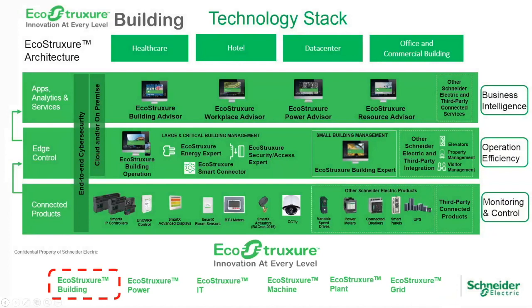If I were here five or ten years ago presenting a BAS system, you might have seen one line at the top representing your IP, internet connectivity, 100 meg. You'd have computers, smartphones, servers at the top, with lines running down to field devices, similar to what we saw in the BAS 101 presentation. Those lines represented BACnet over MSTP, which is how most buildings are connected now if they have BACnet, communicating at a baud rate of 76.8 kbps. It's not very fast, but it's been good enough for what buildings have done.